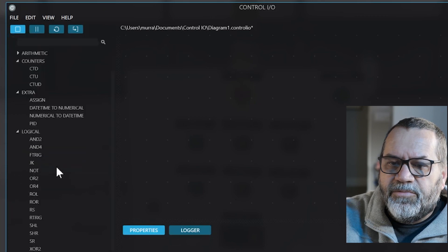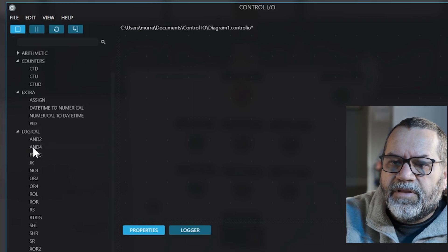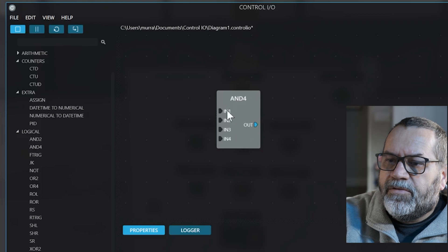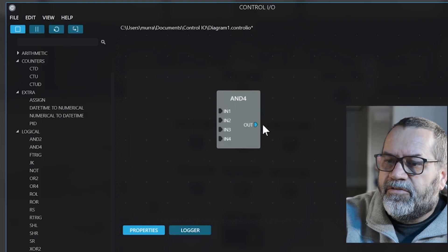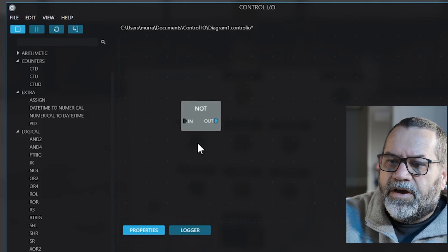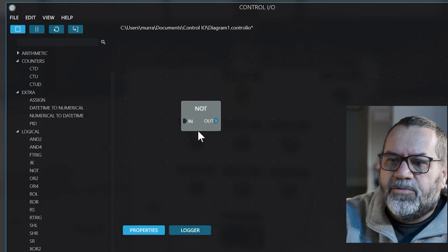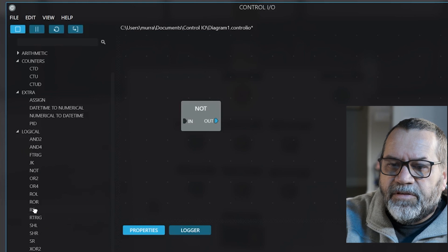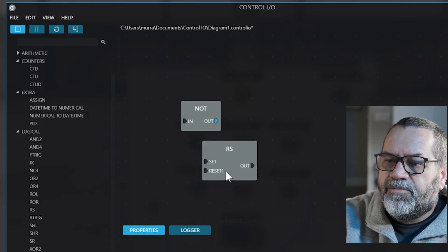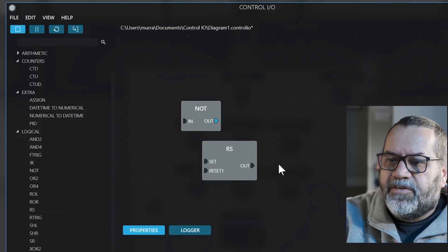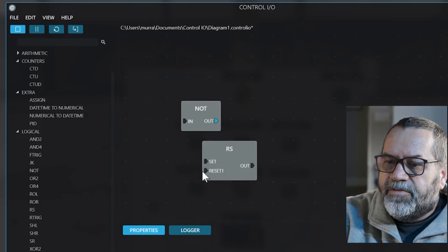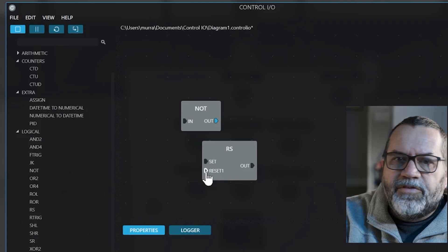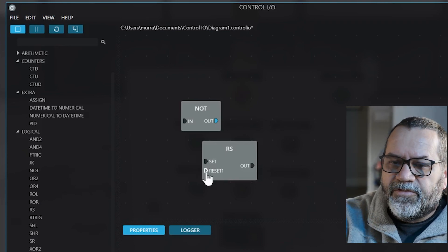Here's logical. We use that quite a bit. And so there's an AND2 and an AND4. So the AND4, you have to have all these conditions true in order to get the output. There's the NOT and that just changes your signal from hot to cold and cold to hot. Now let's see, the reset, set and reset. That's a very handy one. You send one signal and it sets the output and it stays as that output until you send a different signal to turn it off. So that's how we, for example, turn a conveyor on with one sensor and then turn it off with a different sensor.